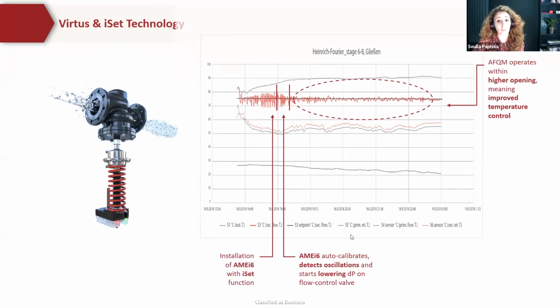So ISET function monitors flow control signals from electronic controller where it detects a signal and is oscillating. And this is enabling it to stabilize the temperature control. It starts intelligently lowering the differential pressure on the flow control valve, and consequently that forces it into a higher opening and out of non-authority range.